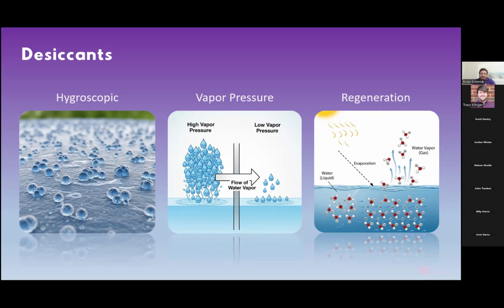We're just talking about a desiccant, a salt, that is absorbed into a liquid. So we can manipulate the concentration of that, and the lower the concentration of that liquid desiccant, the lower the vapor pressure. The lower the vapor pressure, the more affinity it has for absorbing moisture. So if we don't want to absorb as much moisture, we want to have more liquid in the liquid desiccant, we just use less heat to evaporate that liquid out of the liquid desiccant. Eventually, this will reach equilibrium. So if we provided zero heat to our system, eventually the liquid desiccant would reach the same vapor pressure as atmosphere, and you would stop having that flow of water vapor. So again, we need to apply heat to reconcentrate that desiccant. The more we concentrate it, the lower the vapor pressure, the more we can absorb moisture in the future.